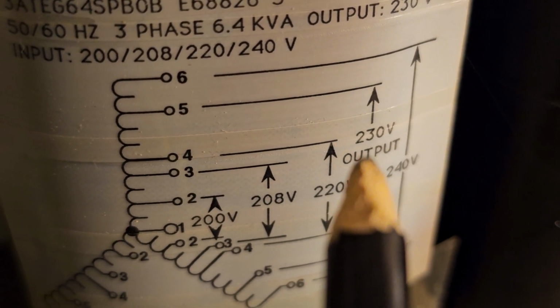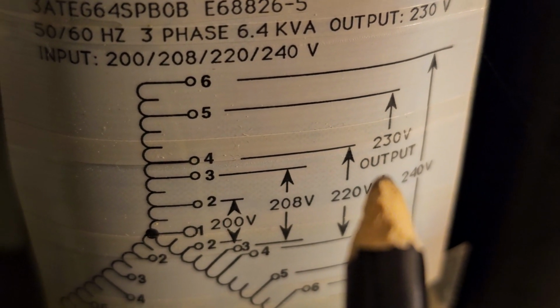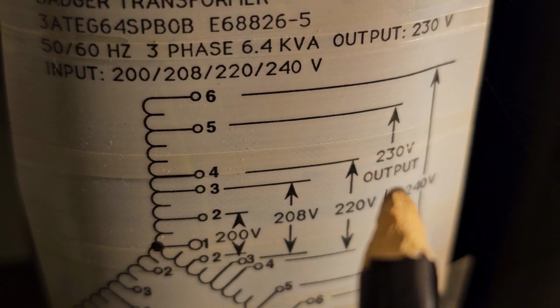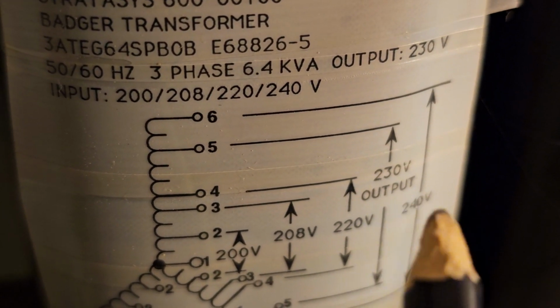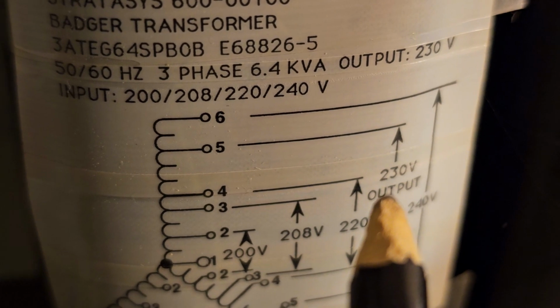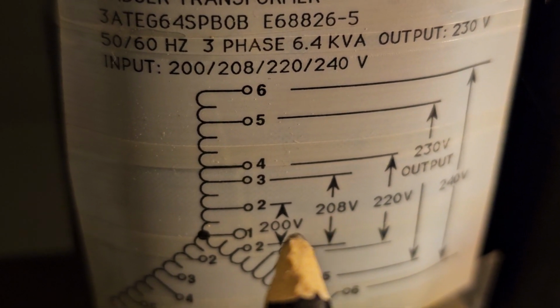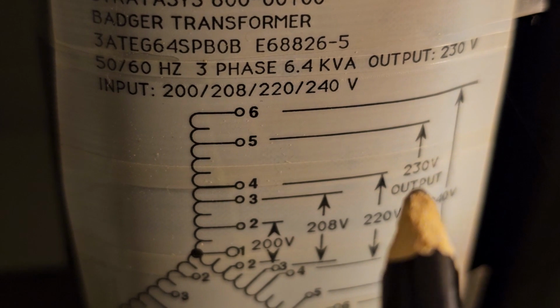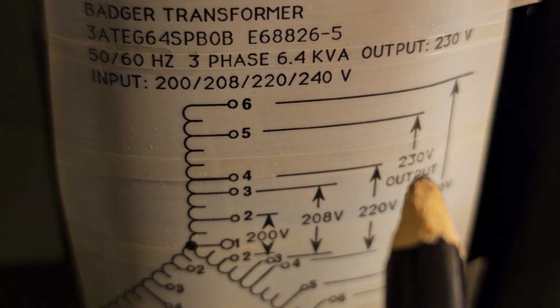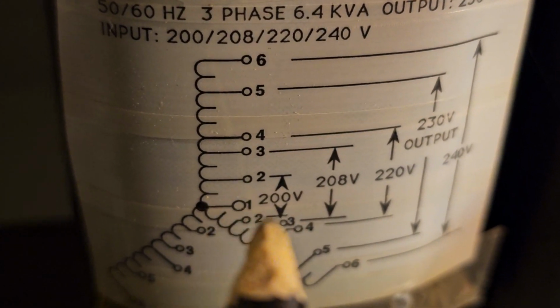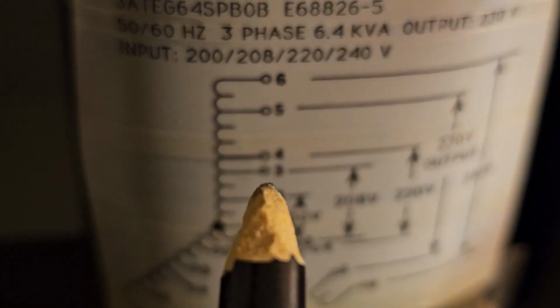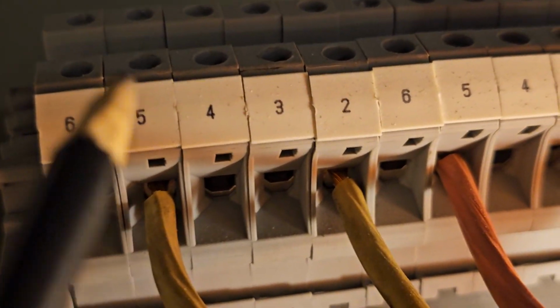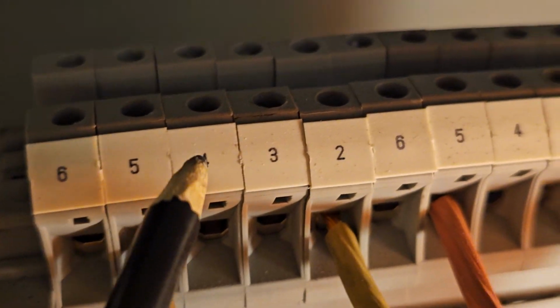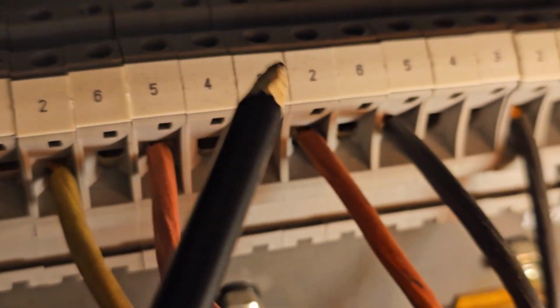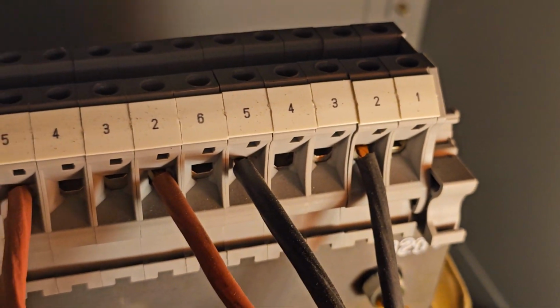230 is the output, so this is a step up, step down transformer. If you put in more than 230 volts, say 240, it'll knock it down to 230. If you put in less, 200, 208, or 220, it'll bump it up to 230. But you've got to make the right connections - there are little numbers here, and the wires go into these numbers, 6 5 4 3 2 1, repeated for each transformer.